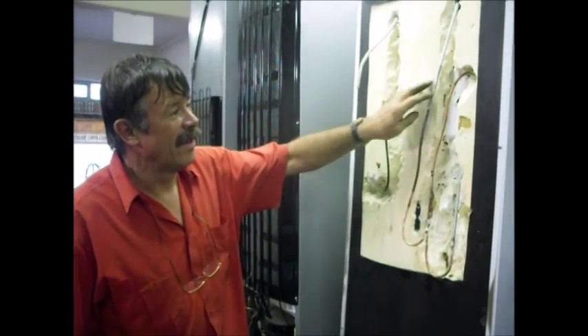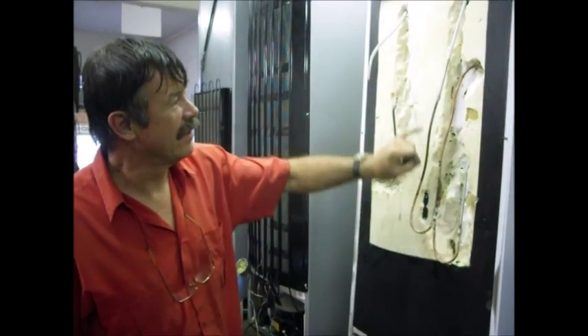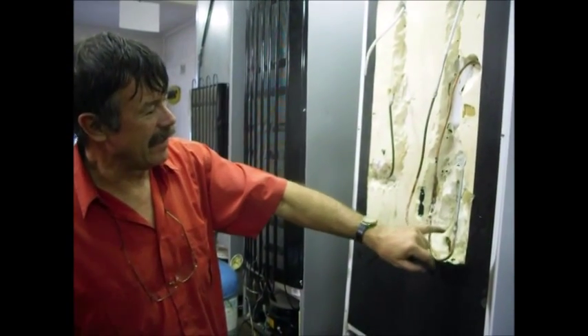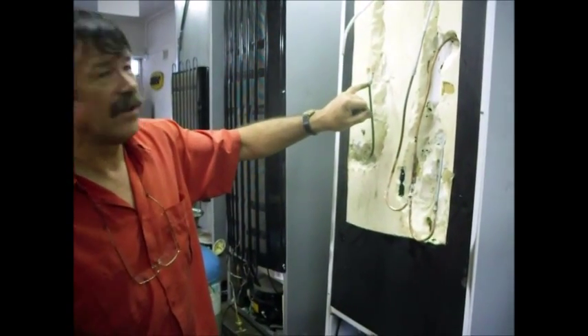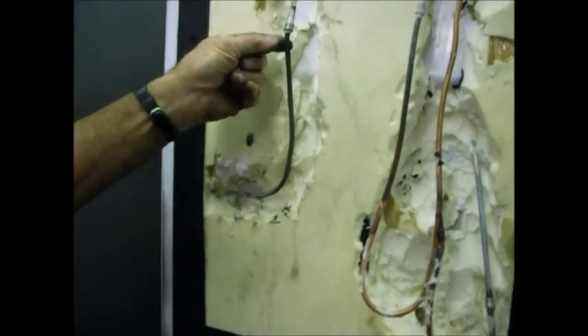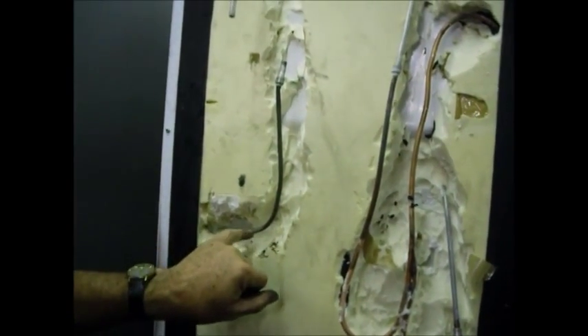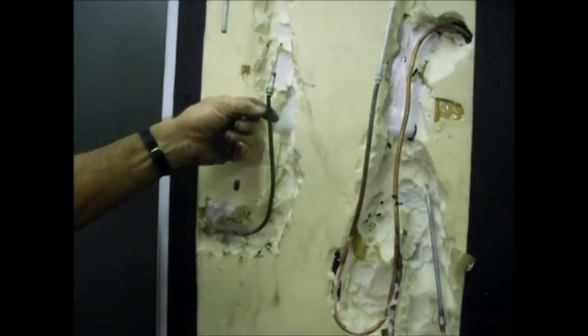This is the Fridgemaster fridge and in the back they've got aluminium, copper and steel pipes. The steel pipes are joined onto the copper and the steel with a lock ring. And in the factory where they put a lock ring on, they clean the anodizing which is that silver bit off the pipe and the pipe rusts through and there's a leak here.